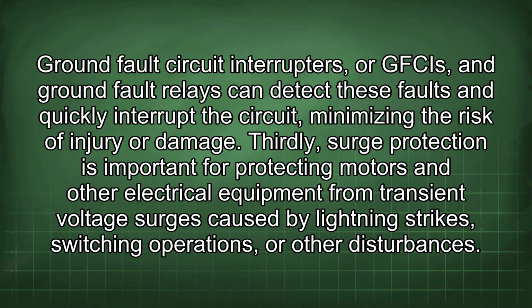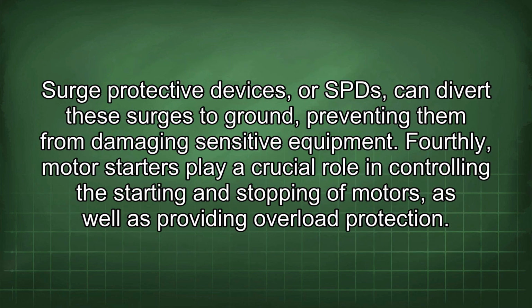Thirdly, surge protection is important for protecting motors and other electrical equipment from transient voltage surges caused by lightning strikes, switching operations, or other disturbances. Surge protective devices, or SPDs, can divert these surges to ground, preventing them from damaging sensitive equipment.